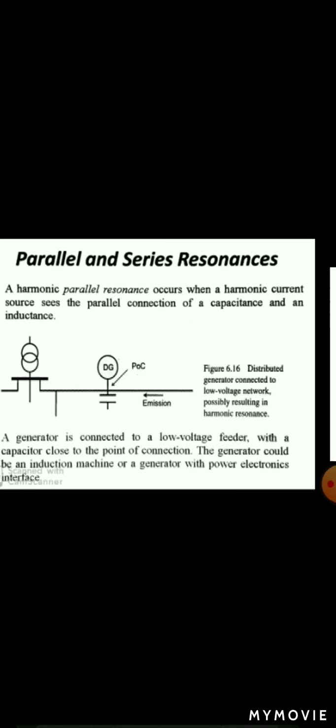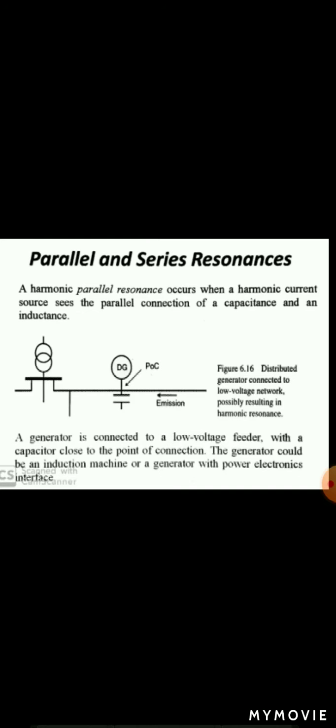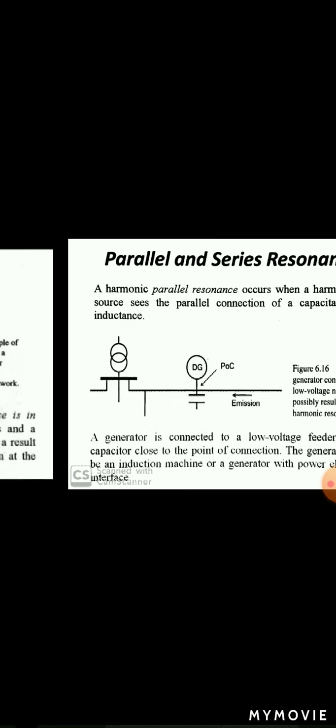Parallel and series resonance. A harmonic parallel resonance occurs when a harmonic current source sees the parallel connection of capacitance and an inductance. By the figure, we can see that a generator is connected to a low-voltage feeder with a capacitor close to the point of connection. The generator could be an induction machine or a generator with power-electronic interface.